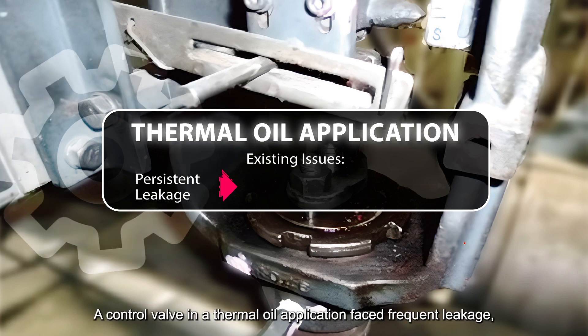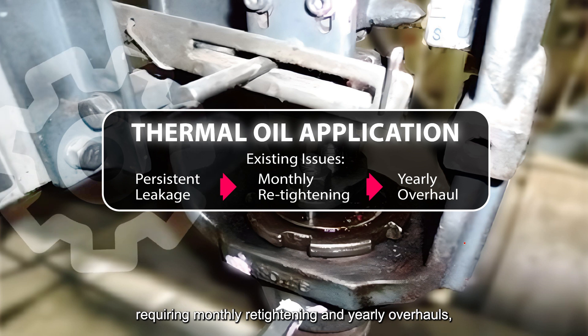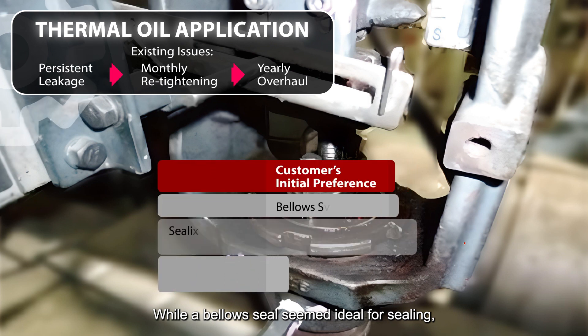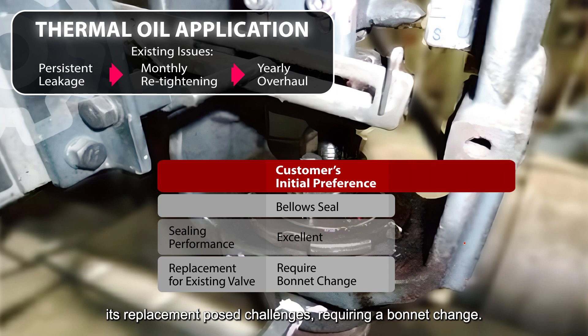Introducing Azbil's case study: a control valve in a thermal oil application faced frequent leakage requiring monthly re-tightening and yearly overhauls, increasing maintenance costs. While a bellows seal seemed ideal for sealing, its replacement posed challenges requiring a bonnet change.